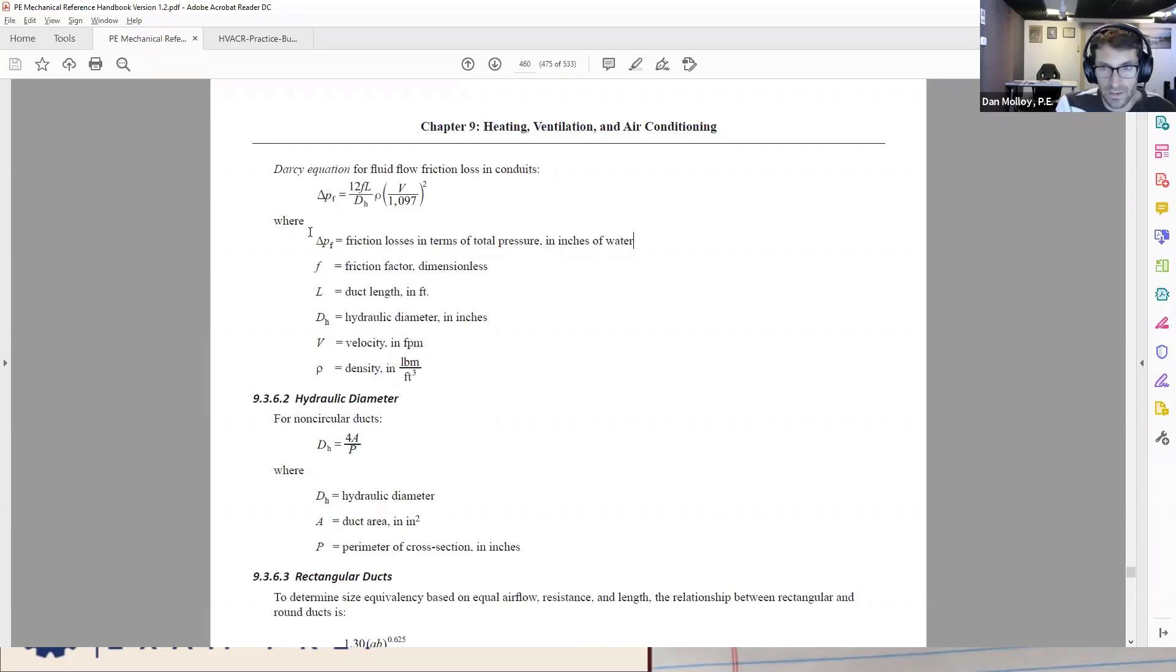So let's try substituting it in. So that formula is delta P sub F and that has to come out in, or at least it ought to come out in inches of water gauge if we put everything in the right way. 12FL over the hydraulic diameter d sub h times the density rho times this term velocity over 1097 squared.